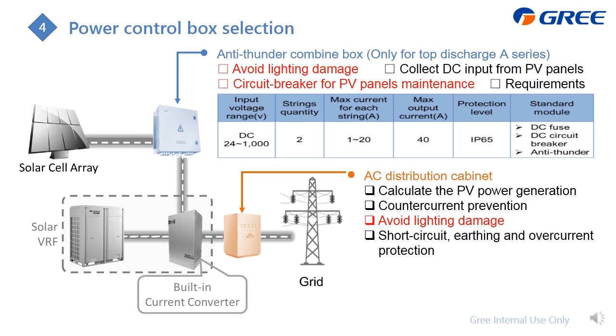Here are the requirements when you're going to do the wiring, especially for the PV panels. The first is don't make a mistake between the positive and negative, which is this plus and minus. Before you connect to the outdoor unit, please check the isolation resistance with the mega meter to ensure it is okay. Also, this cable requires protection.